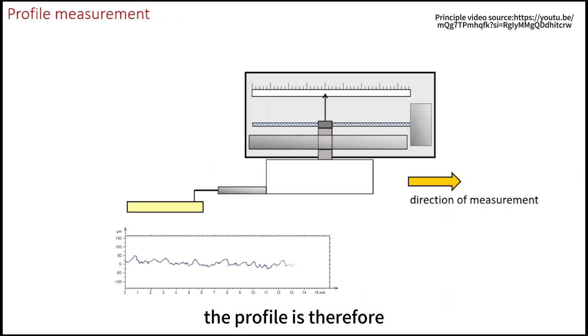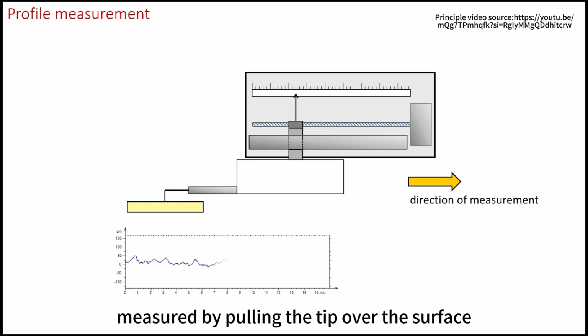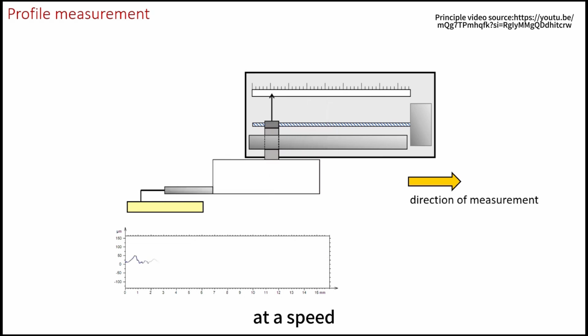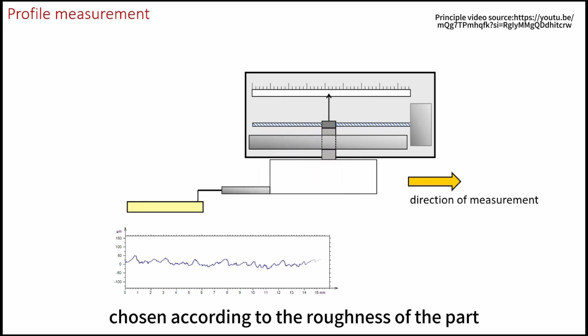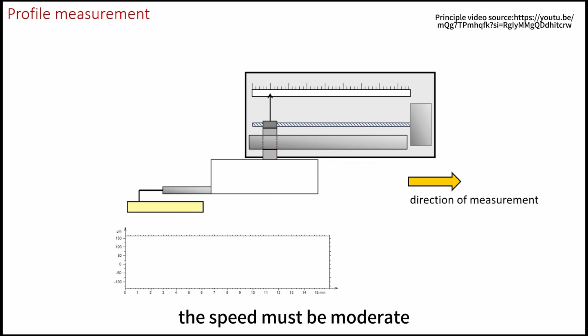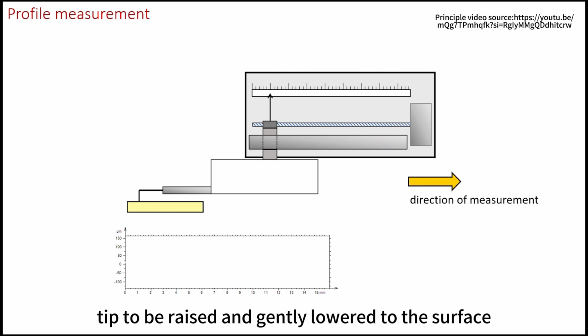The profile is therefore measured, by pulling the tip over the surface, at a speed chosen according to the roughness of the part. The speed must be moderate, so as not to risk bouncing the stylus, or damaging the surface or the tip. Some modern profilometers allow the tip to be raised and gently lowered to the surface.